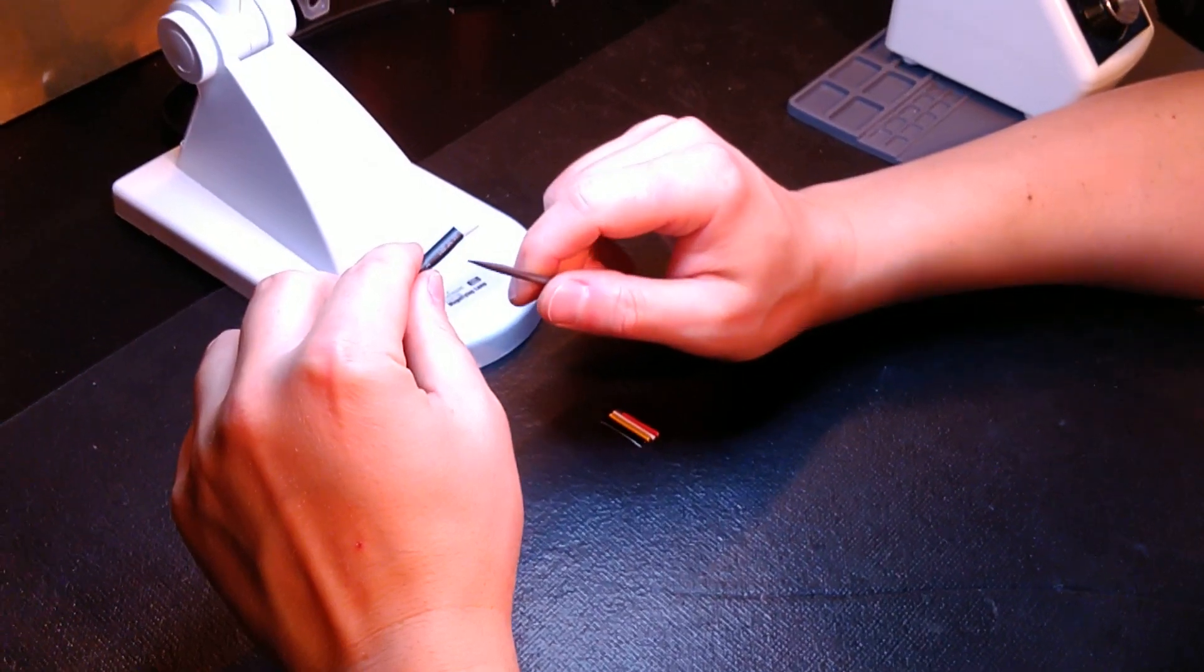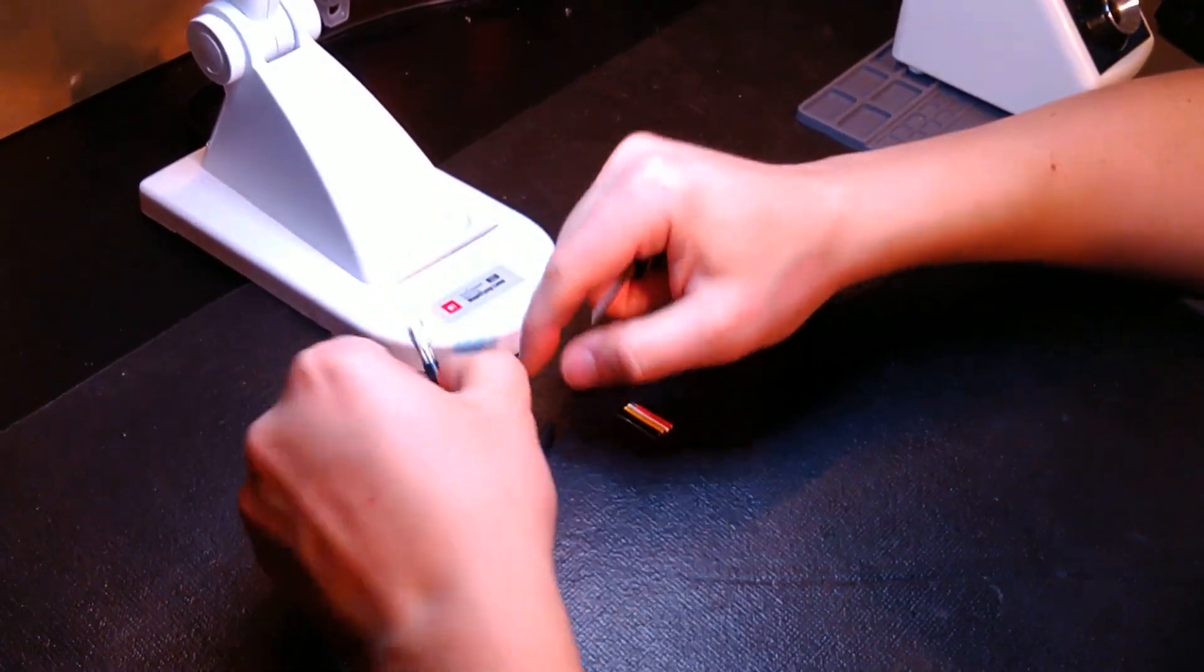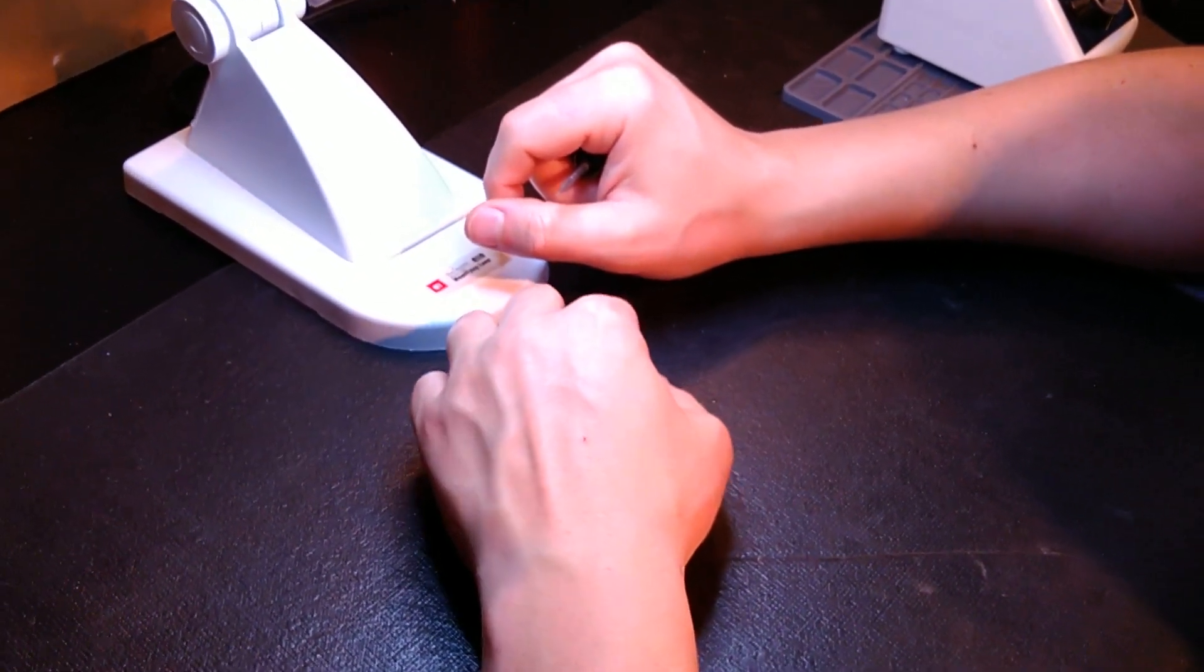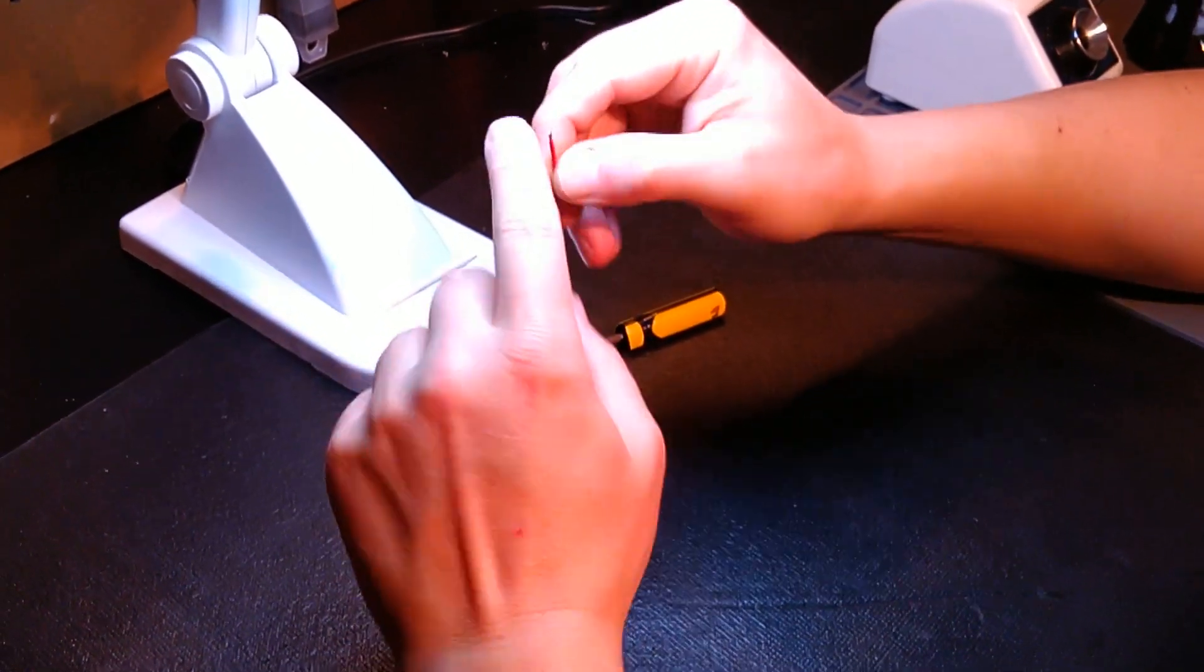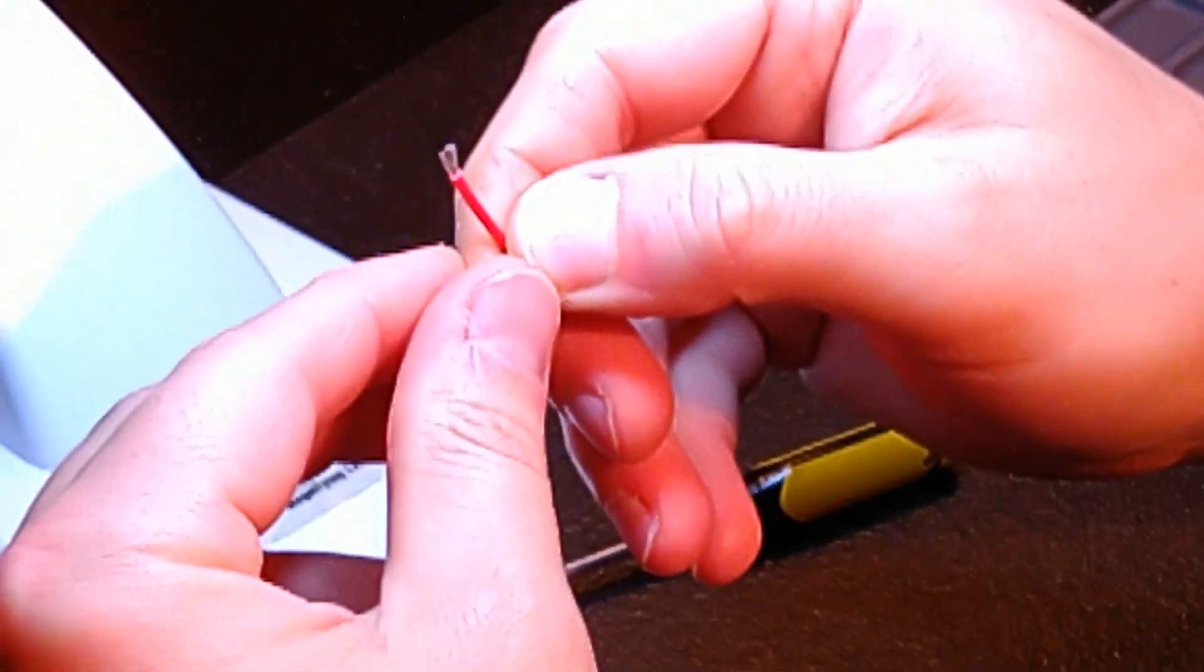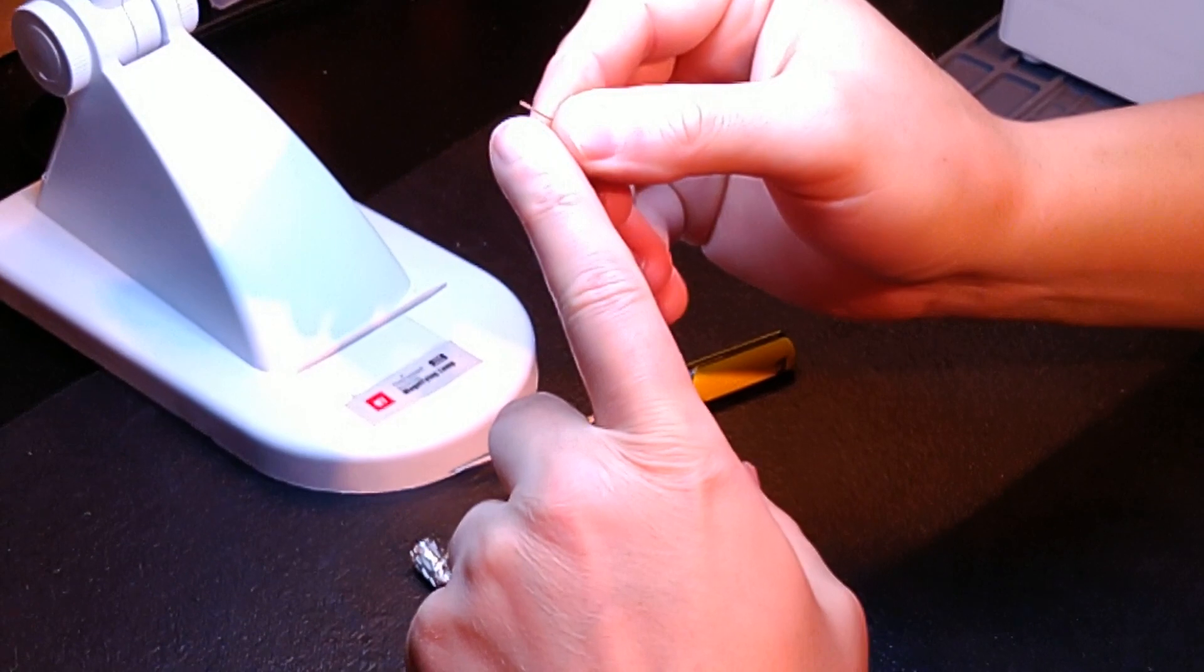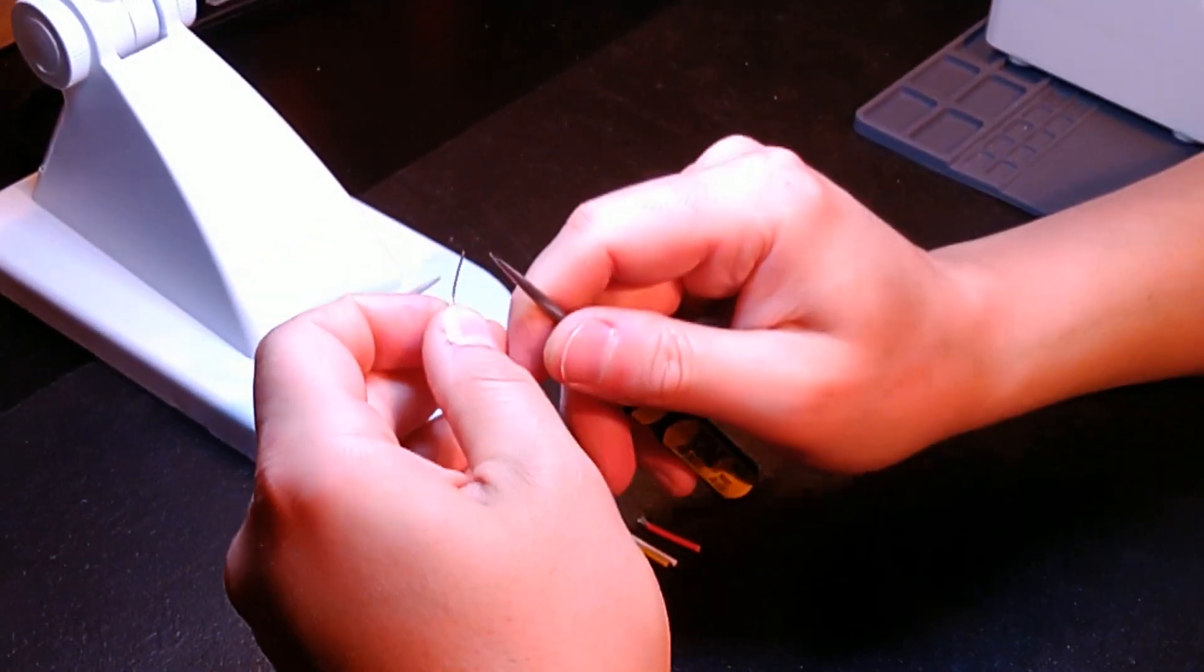This cable is rated to 300 volts, it is an 80 degrees Celsius temperature-rated cable, so super soft, really easy to work with. One question I get a lot is, are the conductors actually copper? Yes, these are copper, and they're actually tinned. You can see here, I'll feather them out a little bit so you can see exactly what we're working with. As far as the shield drain, it is preformed so you guys do not have to do anything—this is the way it's installed in the cable.